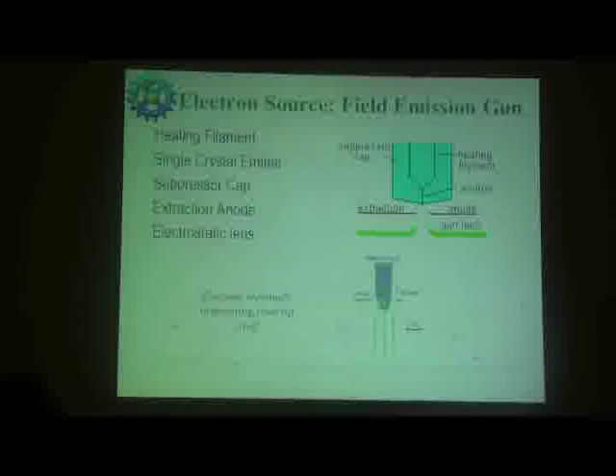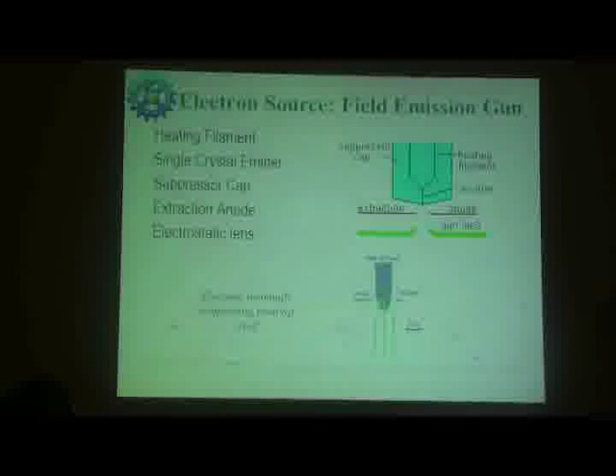But here the tungsten oxidizes easily, so you have to keep it in very high vacuum when you use a field emission gun. If it is allowed to go even to the level of 10⁻⁶ torr, it will get oxidized and you will not be able to use it, and you will not get reproducibility of the electron emission. That's why, though the field emission gun is important, at the same time the maintenance is very high. You have to keep it always in vacuum without oxidizing the tungsten crystal. So this looks like the tungsten filament crystal for field emission.